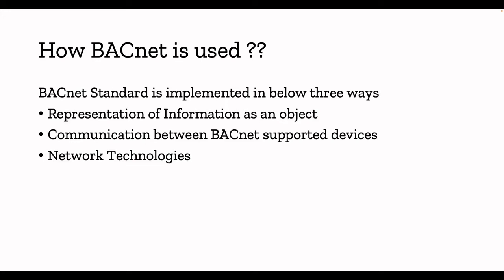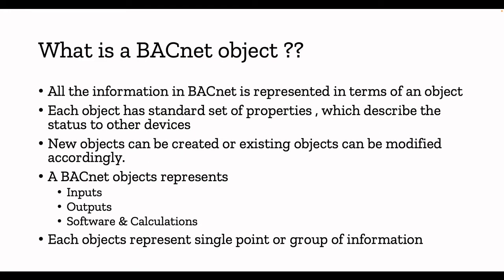We will see a list of network technologies supported by BACnet, and we'll focus mainly on BACnet/IP, since in the Internet of Things today everything is IP-based. So what is a BACnet object? All information in BACnet is represented in terms of an object. Each object has a standard set of properties which describe the status to other devices. If one BACnet device needs to request data from another, it calls the object, specifies what property it wants to read, sends the request, and gets the data.